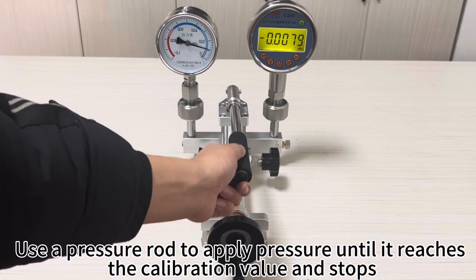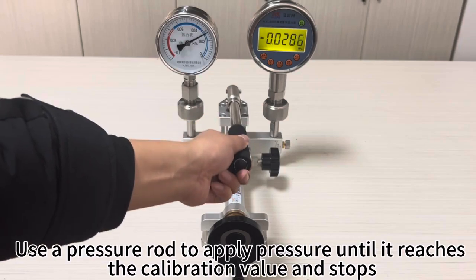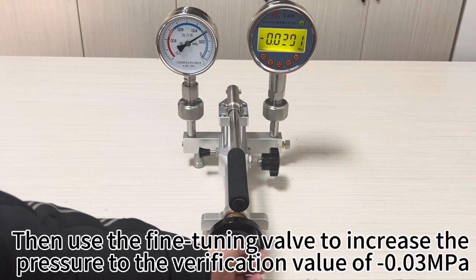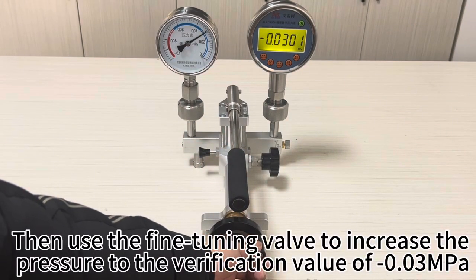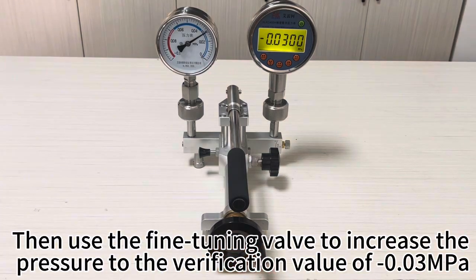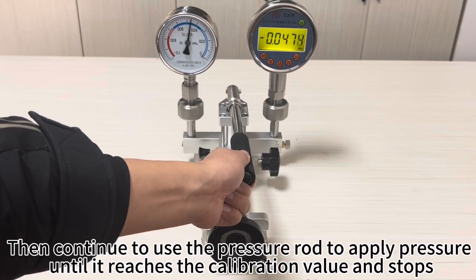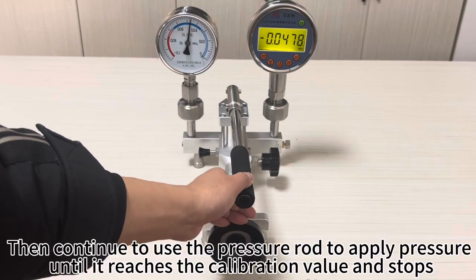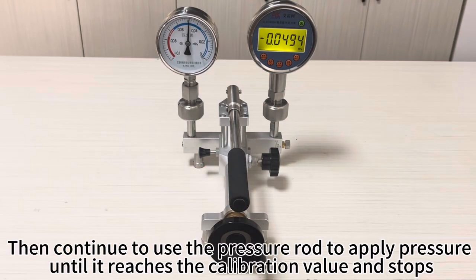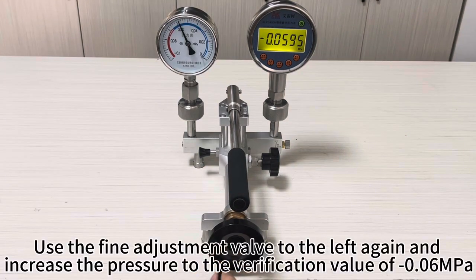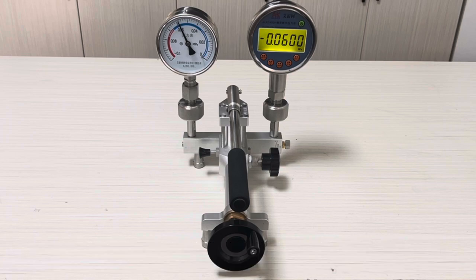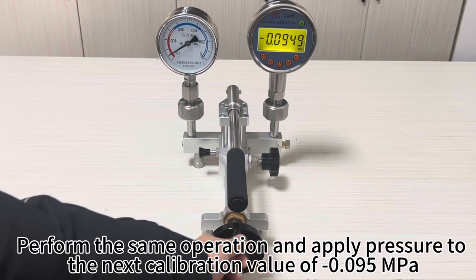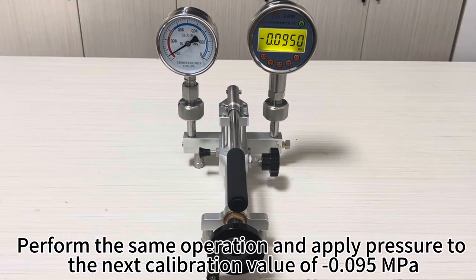Use the pressure rod to apply pressure until it reaches the calibration value and stops. Then use the fine-tuning valve to increase the pressure to the verification value of -0.03 MPa. Then continue to use the pressure rod to apply pressure until it reaches the calibration value and stops. Use the fine adjustment valve to the left and increase the pressure to the verification value of -0.06 MPa. Perform the same operation and apply pressure to the next calibration value of -0.095 MPa.